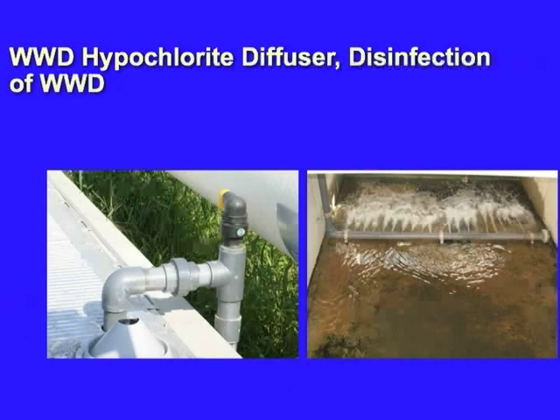All right, here's the diffuser. This is a picture that was taken before they got all the covers out there, to show the motive water shooting into the incoming stream there. You can kind of see that if you're standing at gate 1900, because they still haven't finished the covers last time I was out there, you could look right in there and see that diffuser pipe. This part's been finished since. You have a little air relief valve right there too. If that's not working well, you could get air in the line. So that's something to look at if you have a problem.